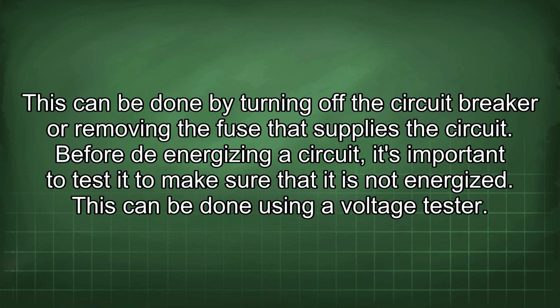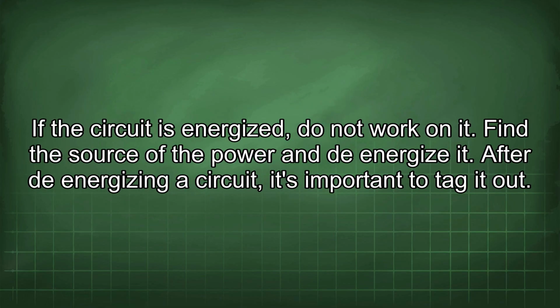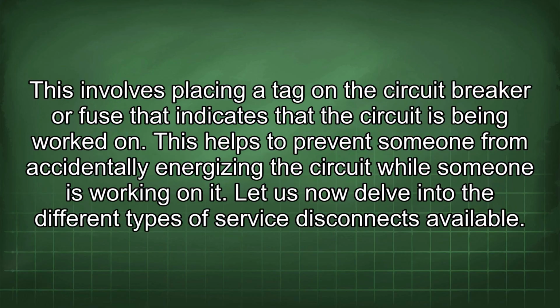Before de-energizing a circuit, it's important to test it to make sure that it is not energized. This can be done using a voltage tester. If the circuit is energized, do not work on it. Find the source of the power and de-energize it. After de-energizing a circuit, it's important to tag it out. This involves placing a tag on the circuit breaker or fuse that indicates that the circuit is being worked on. This helps to prevent someone from accidentally energizing the circuit while someone is working on it.